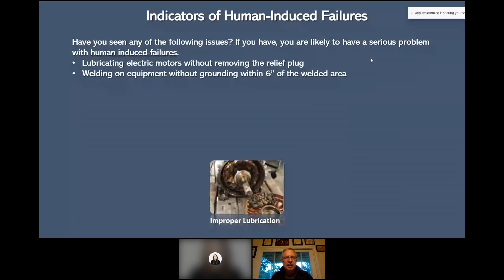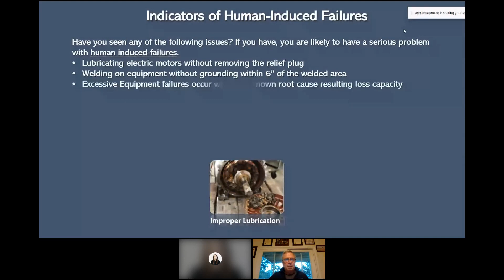I said, so let's walk around outside the plant. This is a massive plant. We walk around outside. The contractors have their welding machines, especially the ones that run off diesel or gasoline, up near the building, and the ground is connected to the building frame. Instead, it should be within 6 inches of the welded area. If it's not, then that current goes through every electrical device, bearings, whatever, and causes major problems.